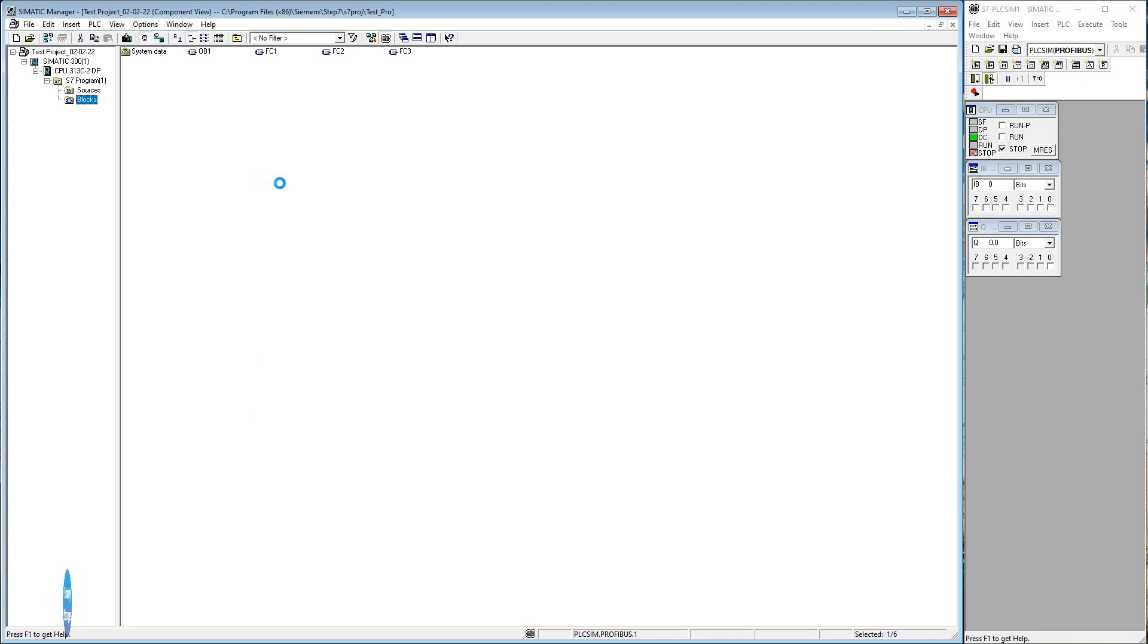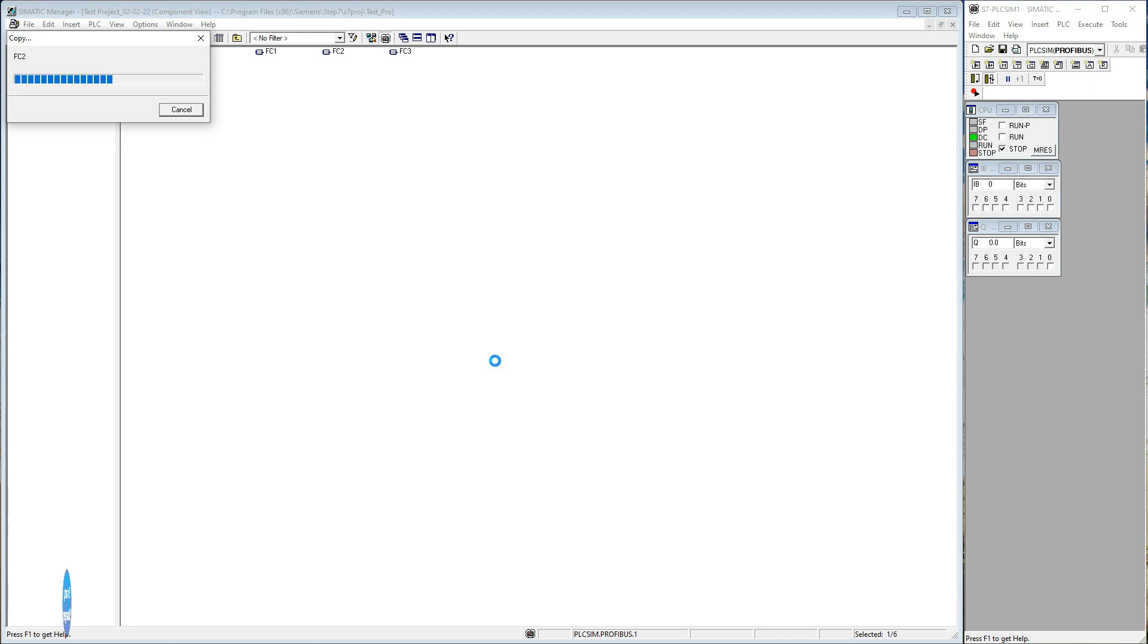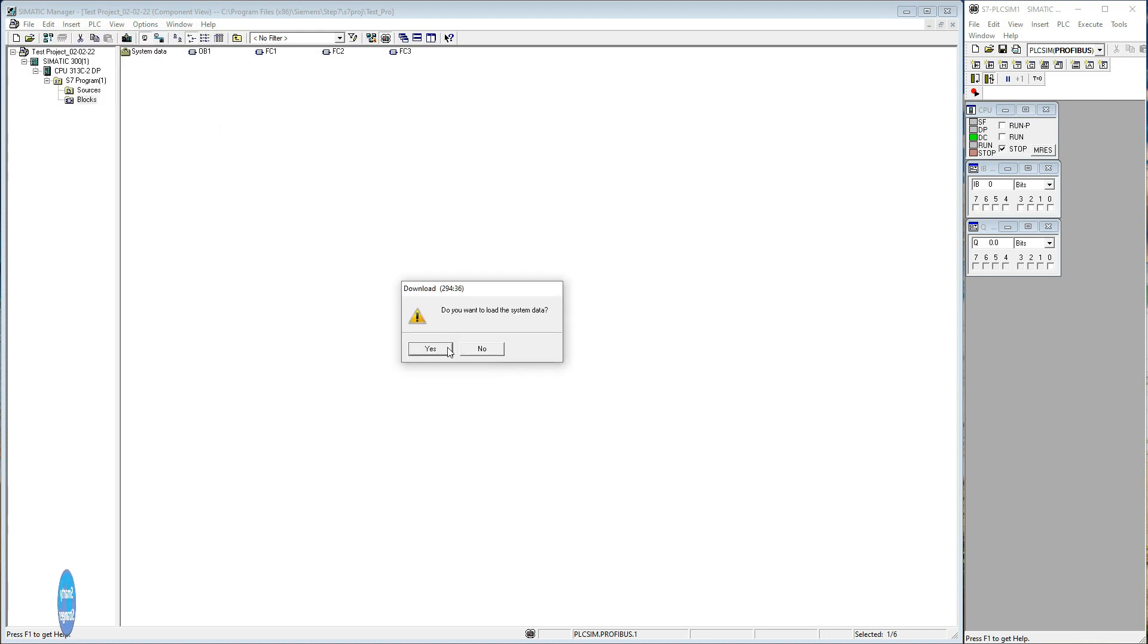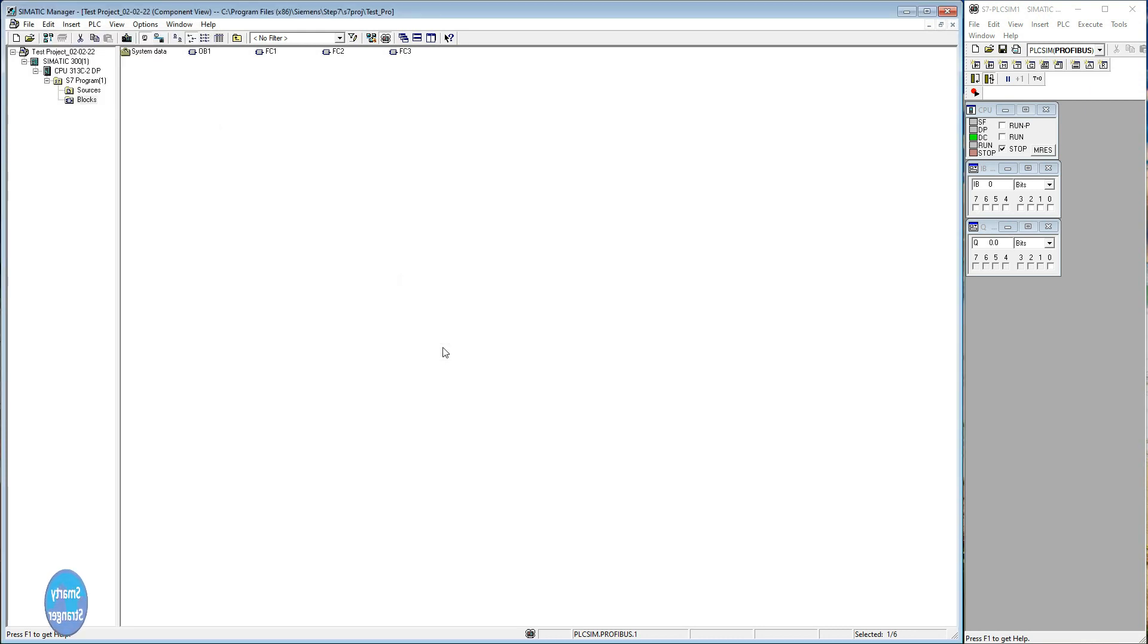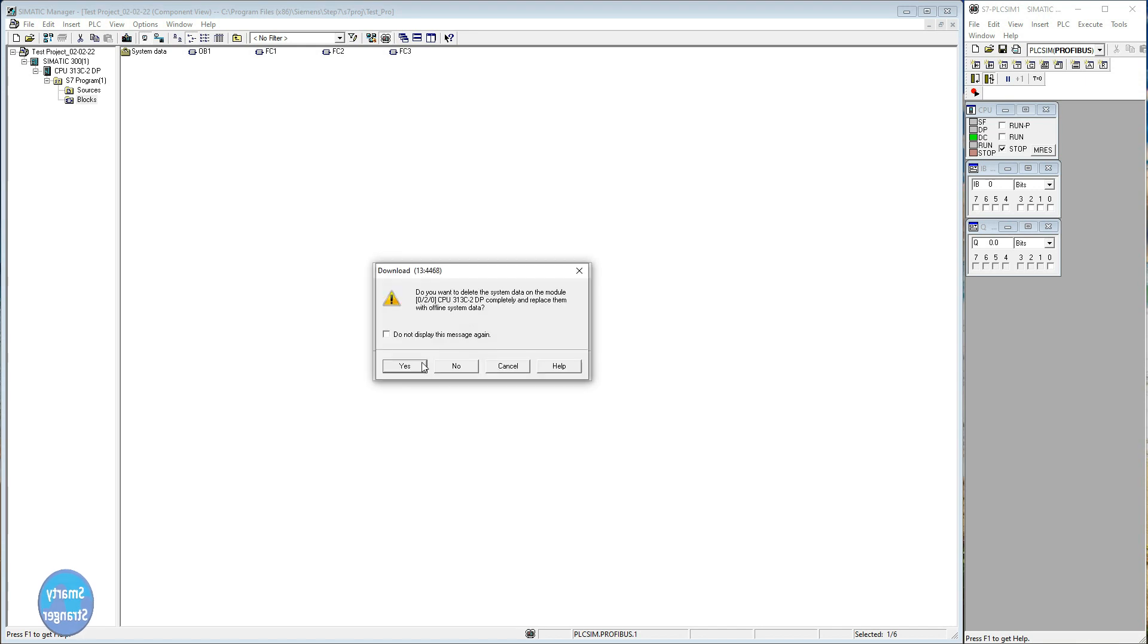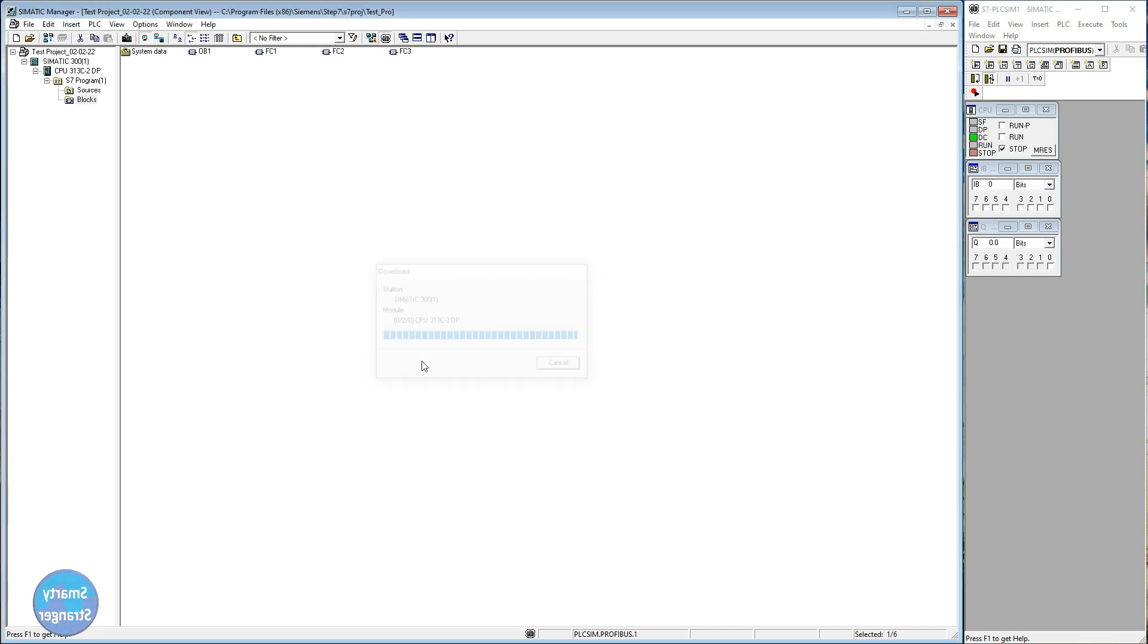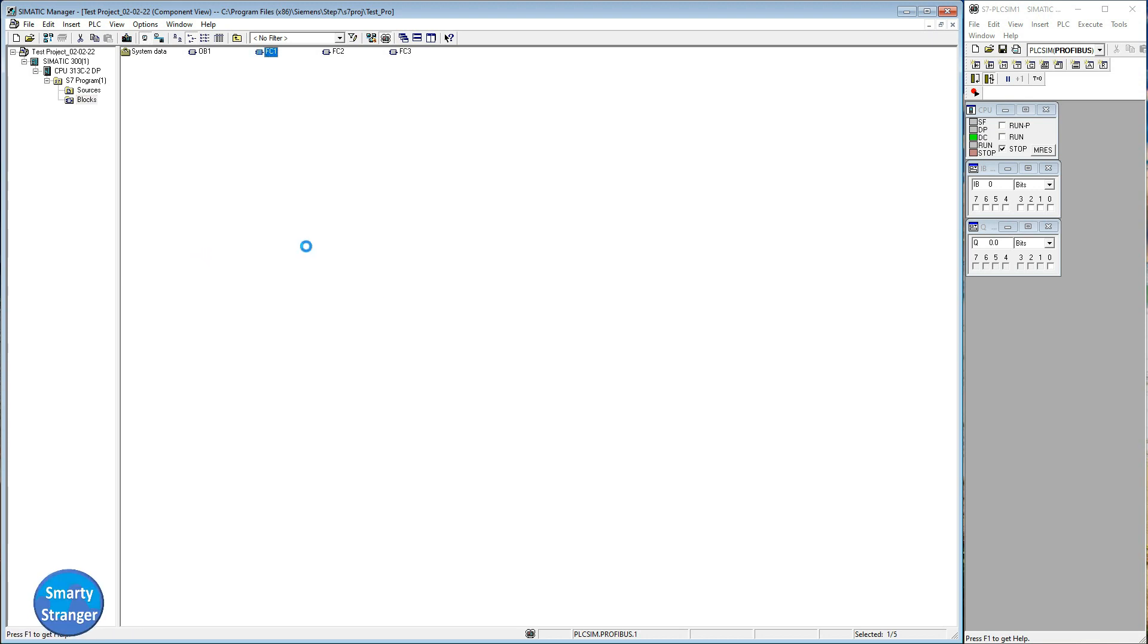So when you require complete downloading, shut down your machine first, put emergency on, then try to download after taking safety precautions. When you made a small modification in logic, you can download it directly. No need for shutdown.